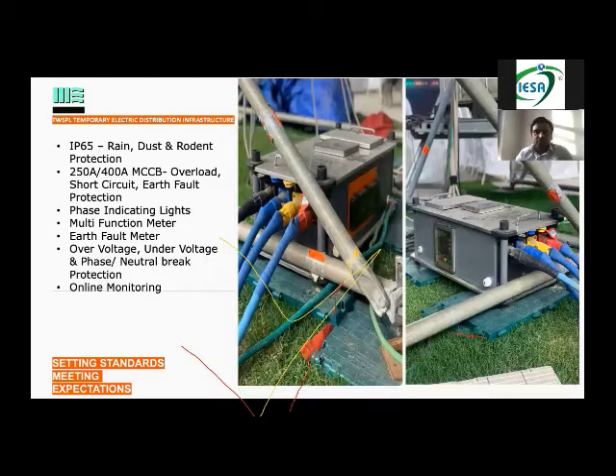And now why it is important to save on your genset cost. Normally, maybe your AC vendor says please give me 10 gensets of 500 kVA, and as an organizer, you give him 10 gensets of 500 kVA. When we are able to monitor the energy each and every hour, we can tell you, boss, you asked for 10 500 kVAs, which is equivalent to maybe 3,500 kilowatts, but during your event you were only using 2,500. So from the next time, you can reduce those costs, which is the major cost on site, the diesel running cost always. Those things are possible with online monitoring.